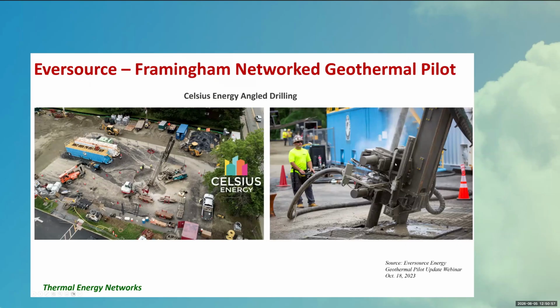This is them drilling at an angle. For the most part we're somewhere between 7 and 12 degrees, because even if you're just 7 degrees off while drilling, when you're going 500, 800, 1,000 feet down, that ends up being hundreds of feet apart from each other. So even though boreholes could be 10 feet apart on the surface, they'll end up hundreds of feet apart below, giving access to a lot more energy than if you had vertical boreholes in a grid pattern.